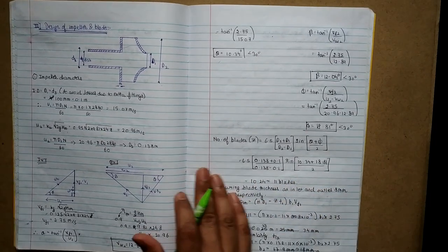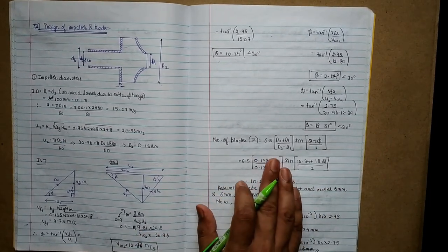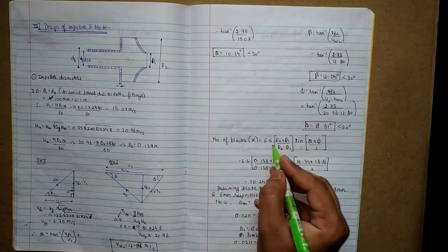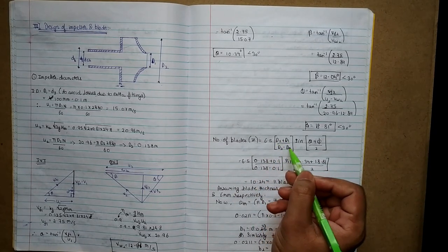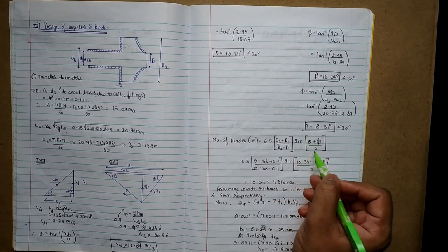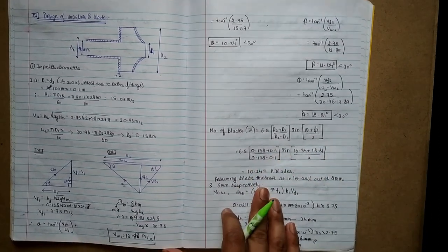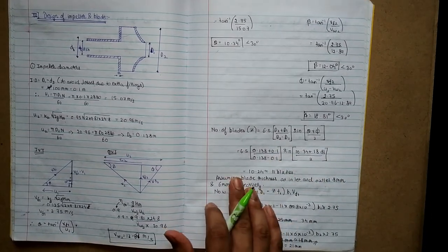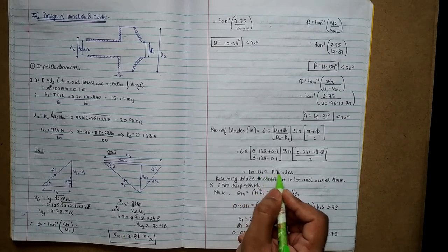After that we calculate the number of blades. The formula is 6.5·[(D2 + D1)/(D2 − D1)]·sin[(θ + φ)/2]. Putting all the required values we get the answer as 10.24, which we round off to 11 blades.